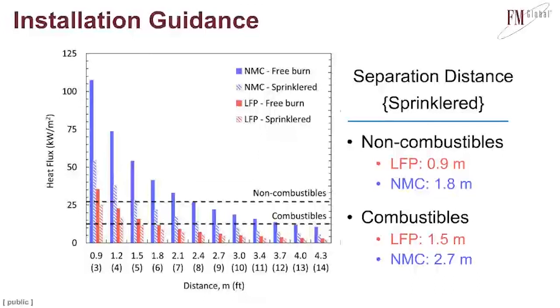And if you start to track that farther away, 4 feet, 5 feet, whatever, you'll eventually start to cross these dashed black lines. Those are the threshold values for non-combustibles. I had that threshold value of 27 kilowatts per meter squared. So once you cross beneath that, it's safe to say that the fire wouldn't damage a non-combustible object. And if we look at combustibles, then you have to keep going. That's the 12.5 kilowatts per meter squared number, and we have to get out to 13 feet away before we think that combustible objects wouldn't be involved in the fire.